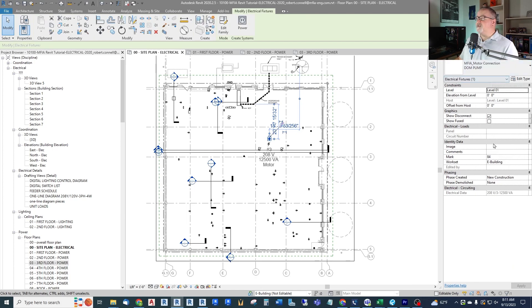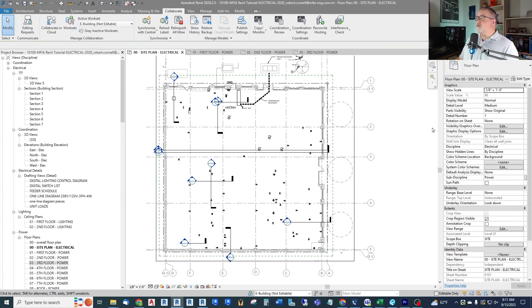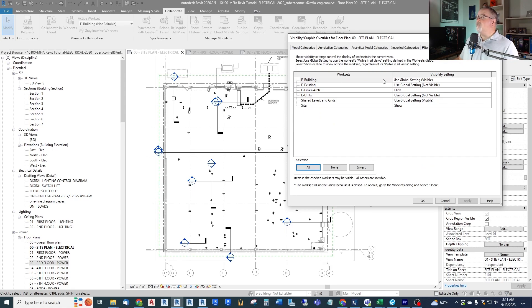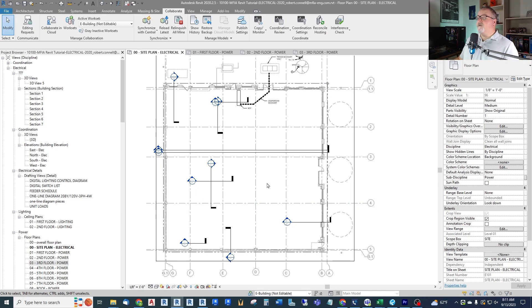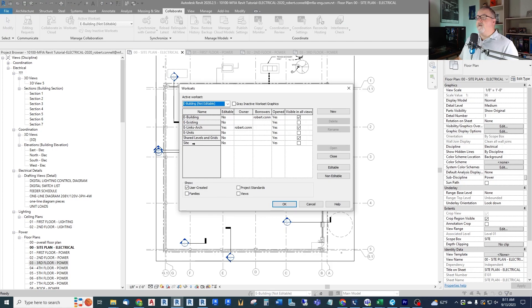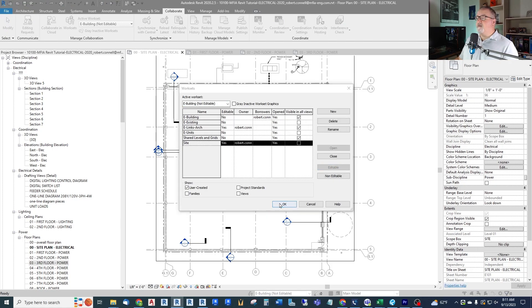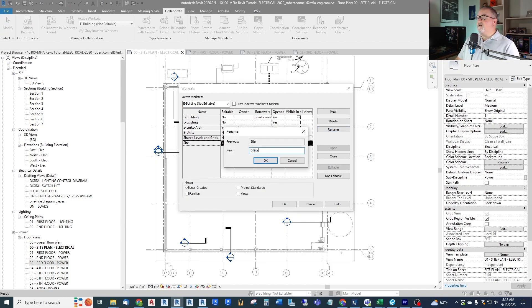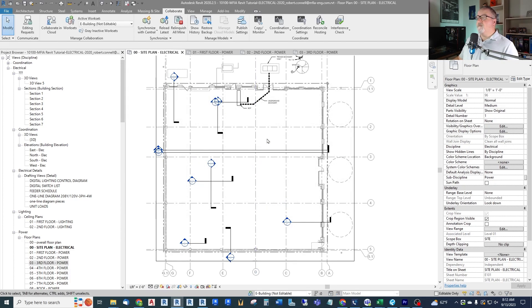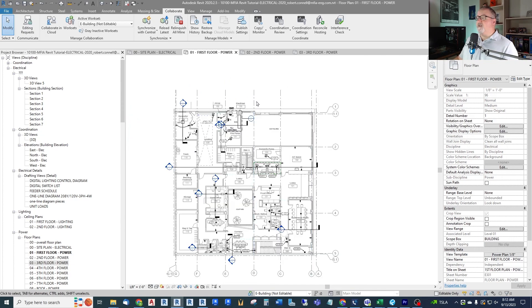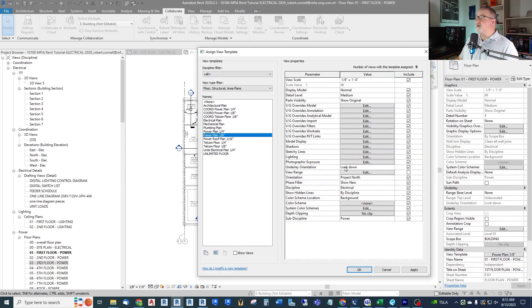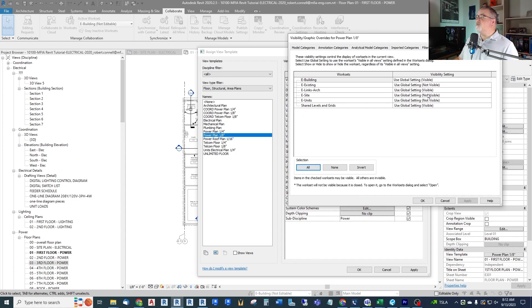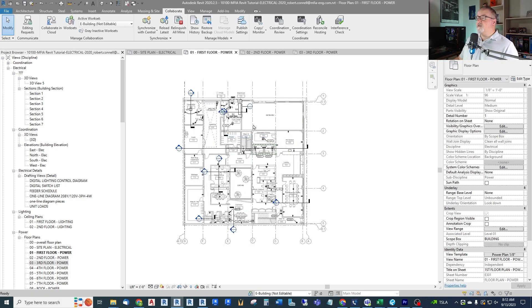Now I click on an element and in its properties I can see the workset is 'e-Building.' I can turn off my e-Building workset in the Worksets tab to hide all that content. I also want to rename the Site workset the same way — make it editable, get out, go back in, rename it to 'e-Site,' make it non-editable. In my first floor power plan I don't see any site work because in the view template I have the Site workset set to not visible.